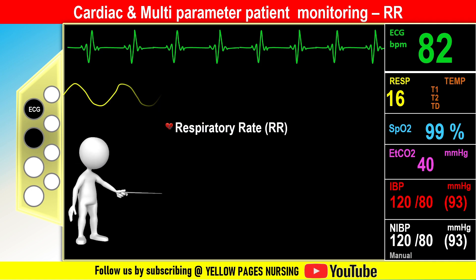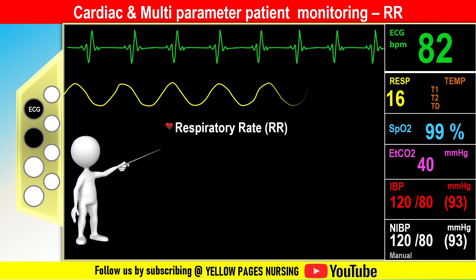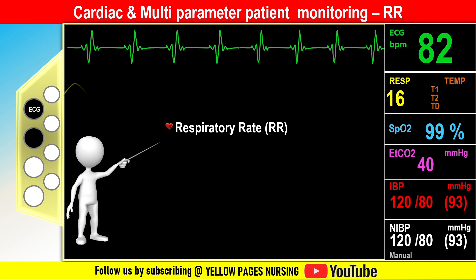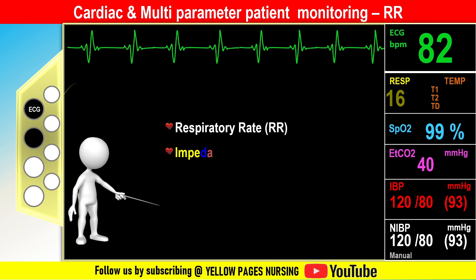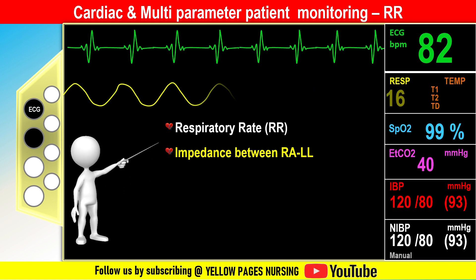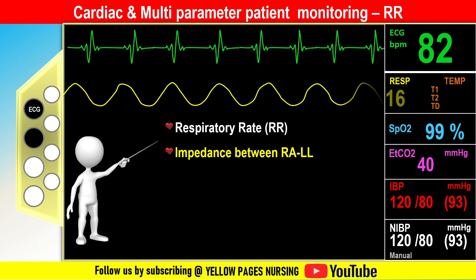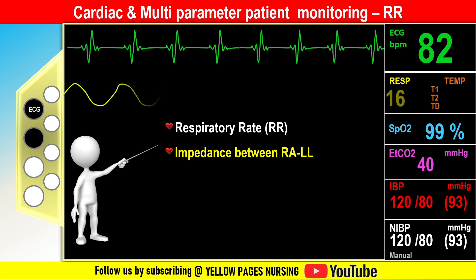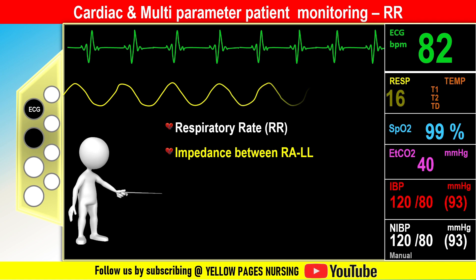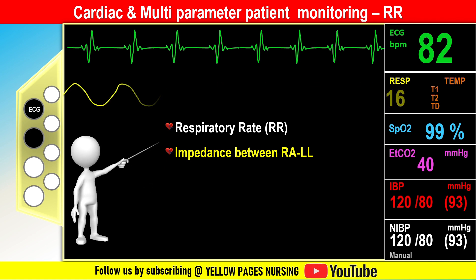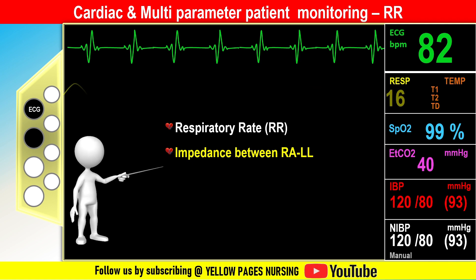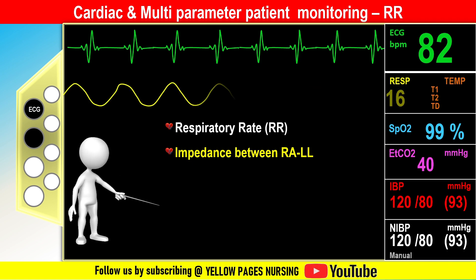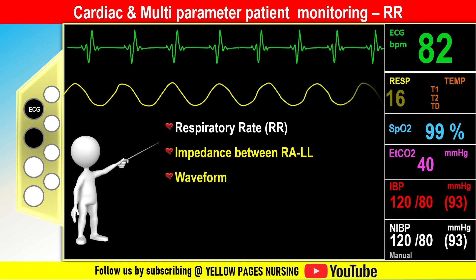Respiratory rate counts the number of breaths per minute, providing information about respiratory function. No specific cable is needed; ECG electrodes are strategically placed on the patient's chest to measure thoracic impedance — the movement of air in and out of the lungs during the breathing cycle. From this thoracic impedance, respiratory rate is calculated.